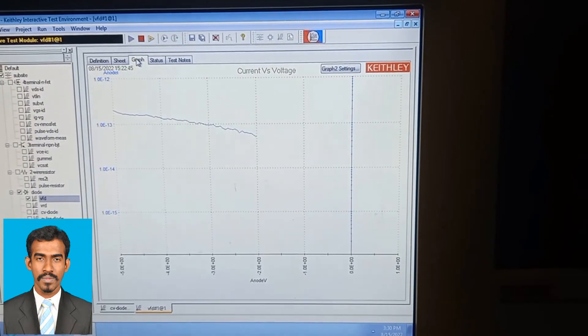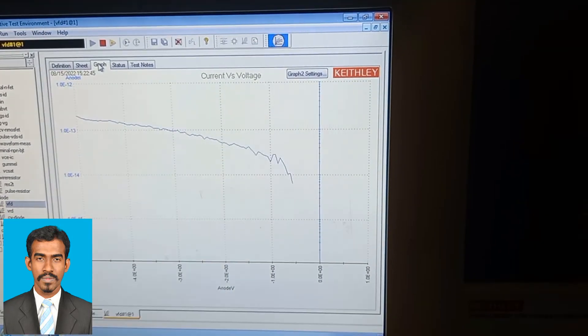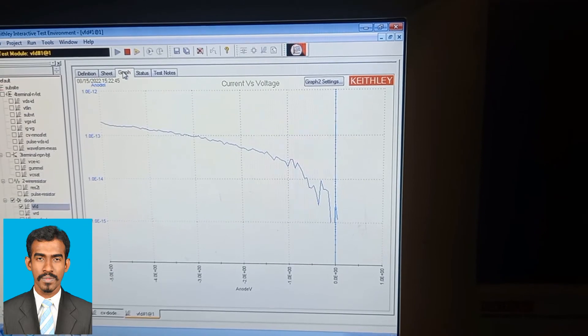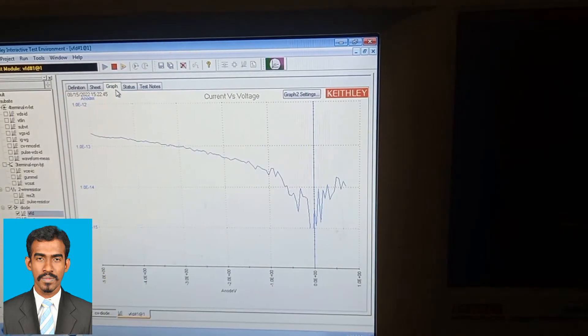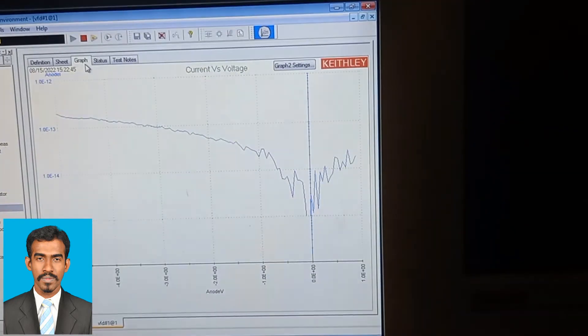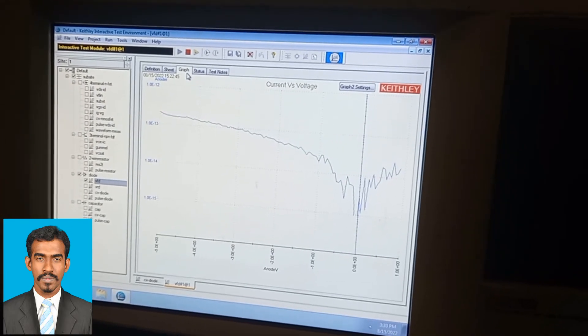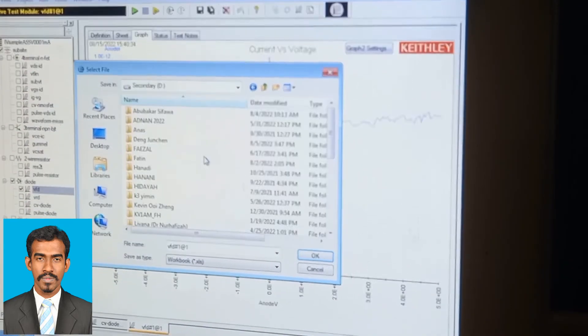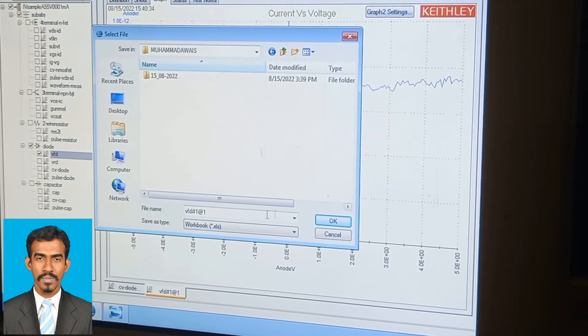Now we are waiting for the graph to complete. You need to wait according to the number of set points you defined. The graph is still in process. Once done, you need to save your results to your desired folder — select the location, click Save All, and close. After taking the measurements, remove your sample from the probe station.